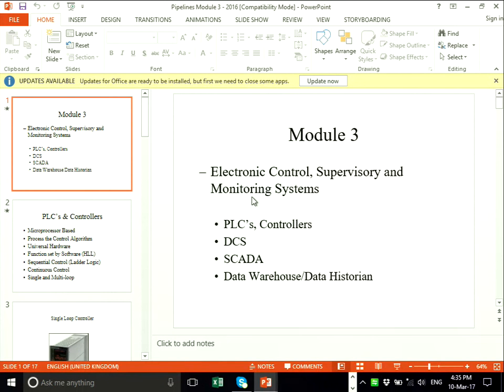So then they tend to put so-called latching filters in. In other words, if it went high, it would latch it in, and then whenever you next ask for the data, even if it was an hour later, you'd still get that alarm, because you could get a very quick event happening in between scans. So it depends on what you need the data for. Say a lot of fiscal data is held on site, but the majority of pressure data, it makes a measurement, and then if it's polled, fine. Otherwise, it waits and it makes another measurement.